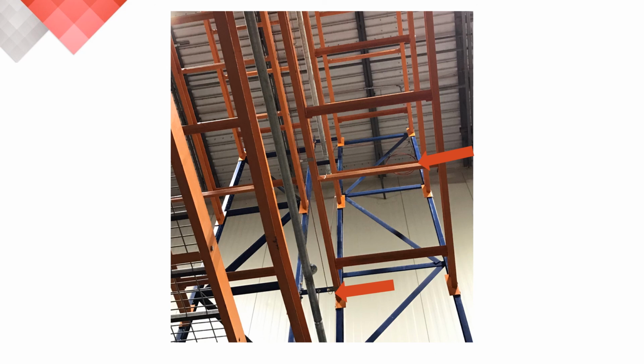Lastly, the detector follows the longitudinal support beam of the racking and remains adjacent to the sprinkler pipe and sprinkler heads throughout the flue space. This is a good image to end our presentation with, as it shows one run of Protectowire for every line of in-rack sprinklers, as required by FM datasheet 8-29.